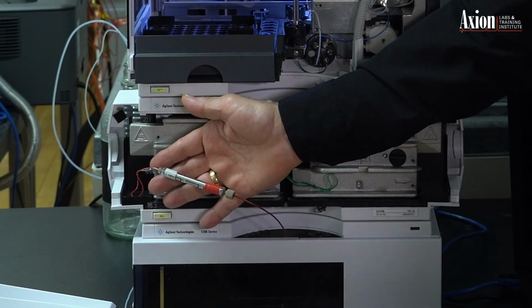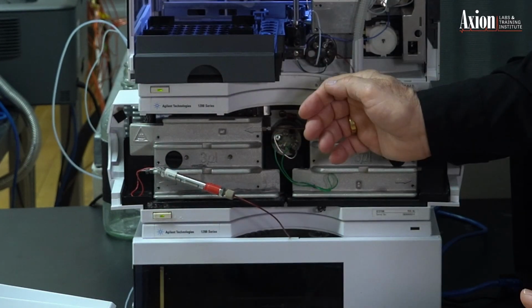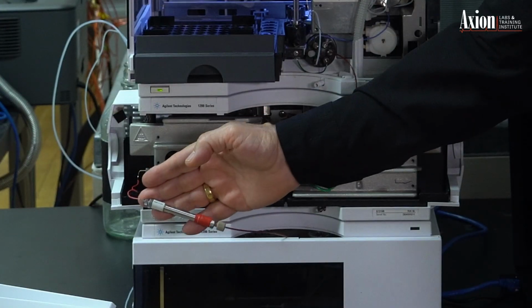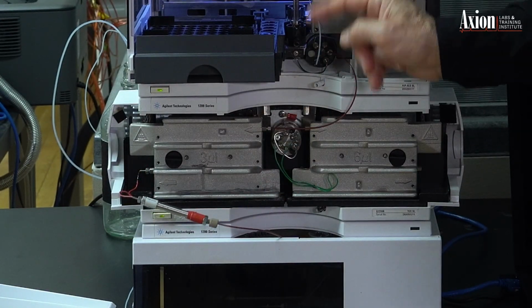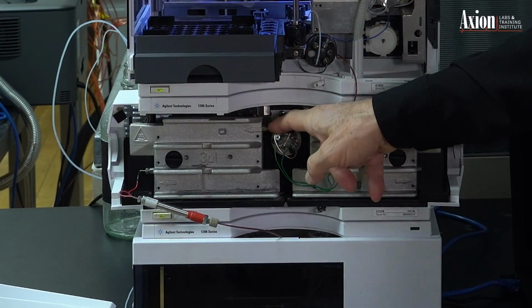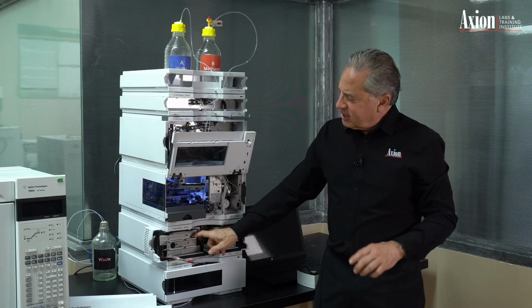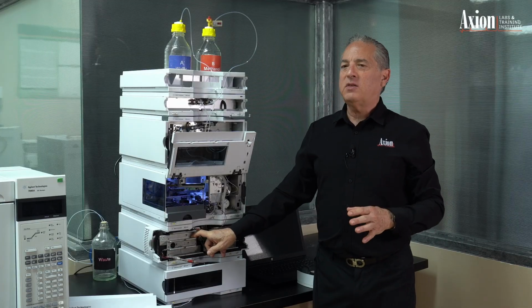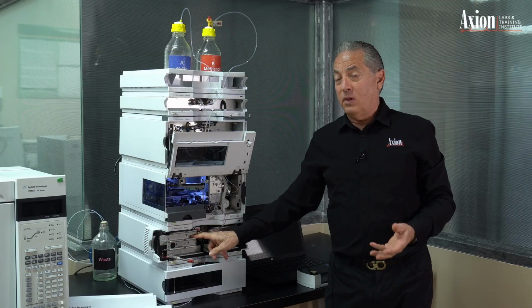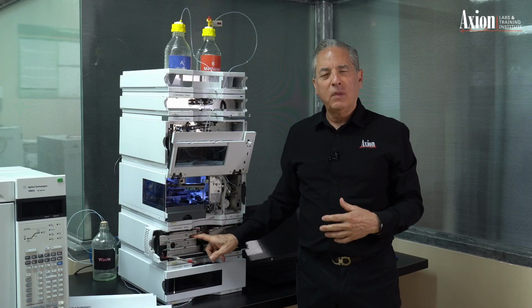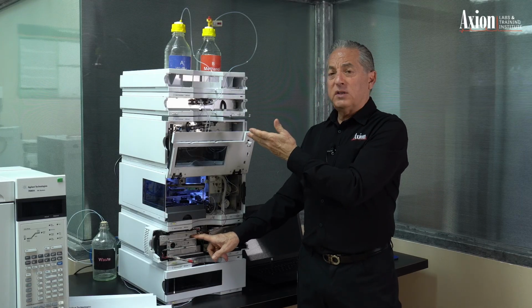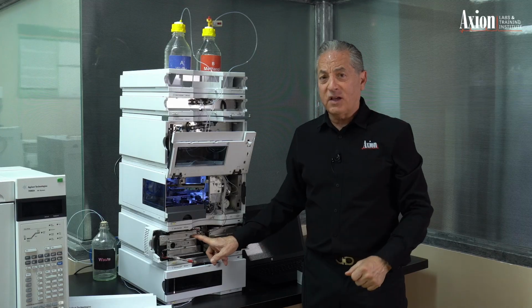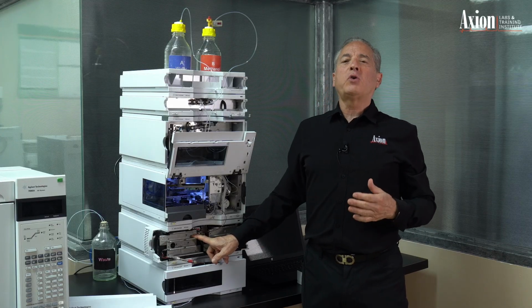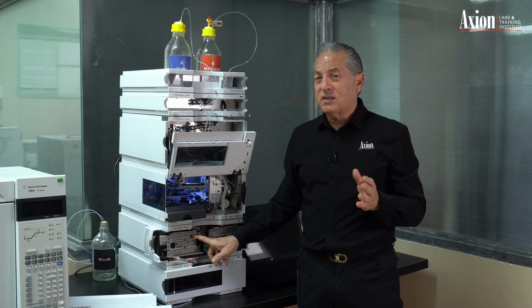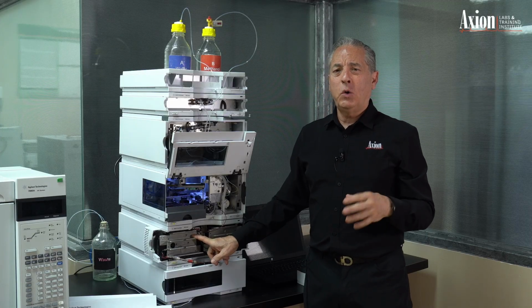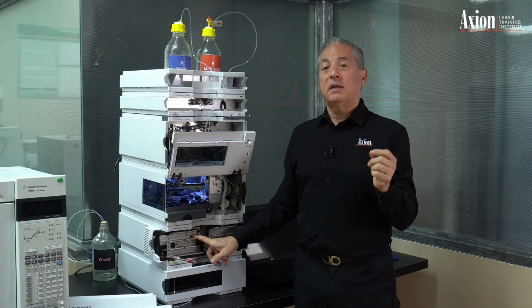It's going to do what you need to get done for most applications. So we have this high pressure flow entering this red tubing. Instead of going directly to the column, the folks at Agilent, they're a little nitpicky. They want to make sure that the temperature of the sample is the same as the temperature of the column. You know, the sample is at 20 degrees Celsius, the column's at 40 degrees Celsius. We don't want to have a temperature gradient across the column because it causes a little bit of noise. So it's nitpicky, it's a small amount, but let's get rid of the noise.